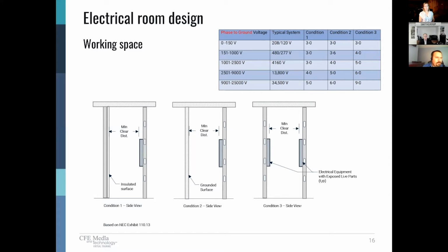And then condition three is the condition where you've got a panel or a switchboard across from another panel or switchboard, where the condition is such that you could have exposed live parts directly across from each other. And so you can see in the table at the top of the screen how that impacts the required depth of the working clearance in front of the panel, or between them in some cases.